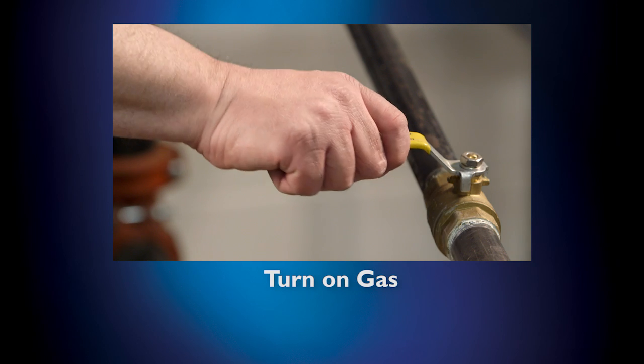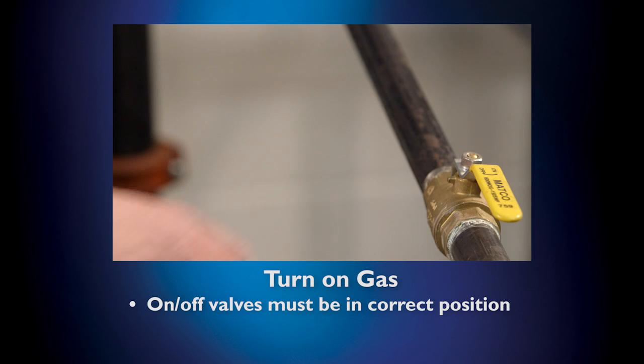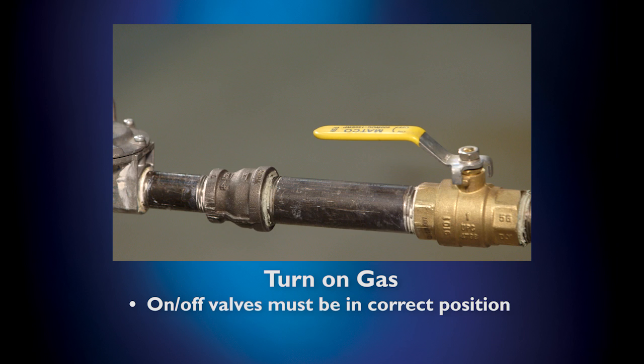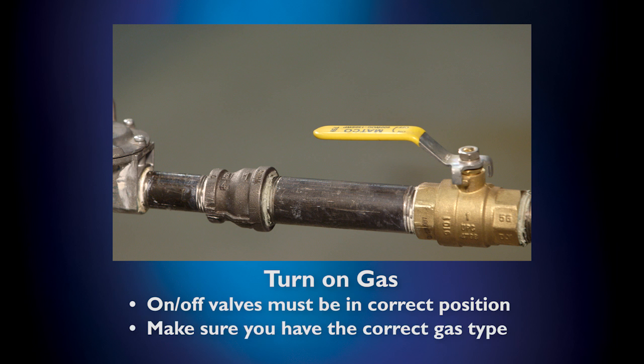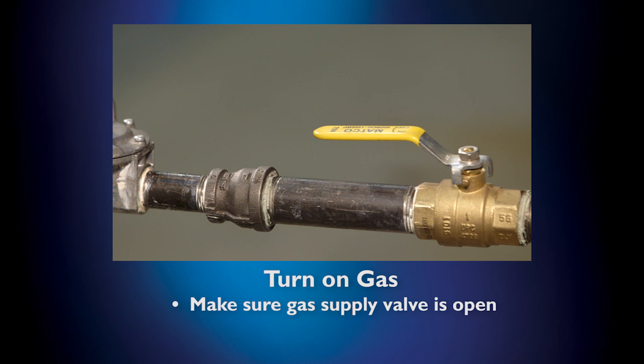Now it's time to turn on the gas. First, make sure all of the system's on-off valves are in the correct position, either open or closed as specified in your unit's manual. Make sure you have the correct gas type. If the available gas type is different than your boiler, the unit must be converted. Later in this presentation, we'll show you how to accomplish this conversion. Make sure the gas supply valve is open. Also, check to make sure there are no gas leaks.